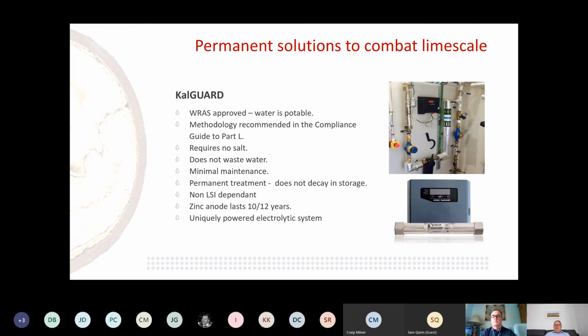There's minimal maintenance really. You've got an optional filter which we recommend. That's a 55 micron filter, which effectively is a series of captive discs on a rack. You could remove those six monthly or annually, depending on the state of your system, separate the discs, give them a really good clean, and reassemble. So again, you don't have to stock spares. Maybe just an O-ring for the bowl, but you're not throwing away cartridges or anything like that.